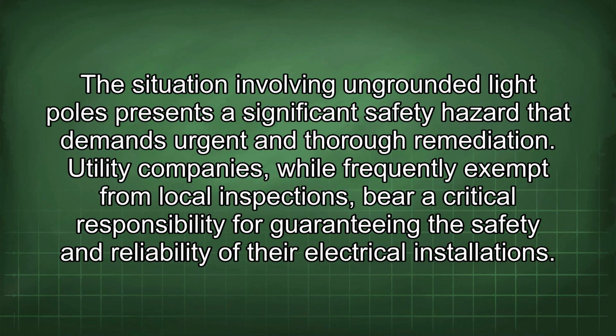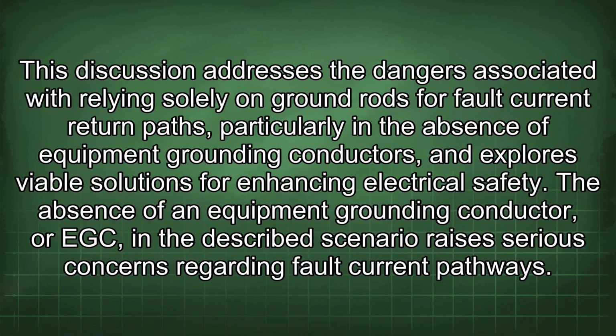The situation involving ungrounded light poles presents a significant safety hazard that demands urgent and thorough remediation. Utility companies, while frequently exempt from local inspections, bear a critical responsibility for guaranteeing the safety and reliability of their electrical installations. This discussion addresses the dangers associated with relying solely on ground rods for fault current return paths, particularly in the absence of equipment grounding conductors, and explores viable solutions for enhancing electrical safety.